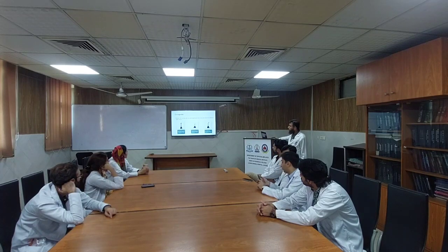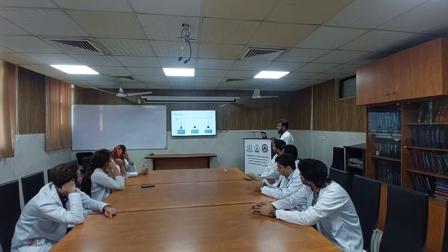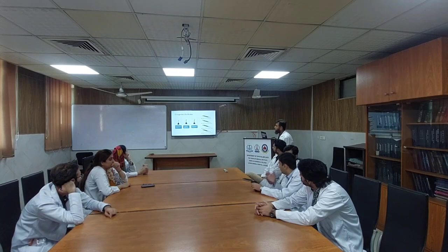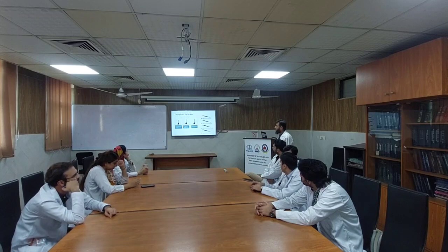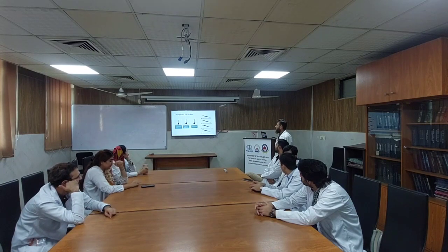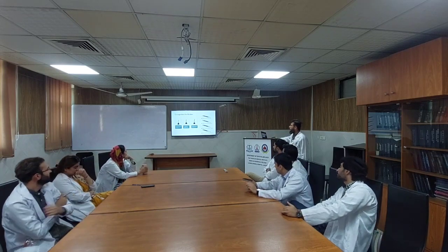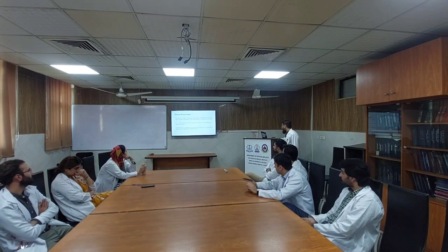These are the different types of probes. In the first picture, this is a 4 by 10 millimeter Collins trichiasis probe. The second one is a 1.5 millimeter curved cataract probe. And the third one is a 3 mm glaucoma probe. These are different probes used in the retina. In the first picture, there is a 2.5 mm standard retinal probe, a 2.5 mm mid-reach retinal probe, and a 2.5 mm extended retinal probe. These are different types of instruments we use: cryoprobe for retinal ball, retina spatula, retina D-shape, and retina bonnet shape.